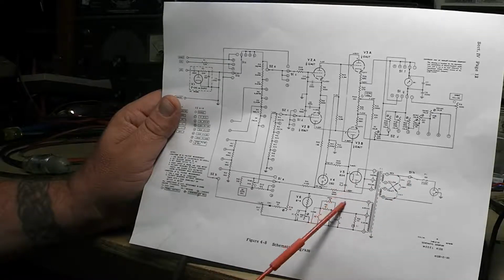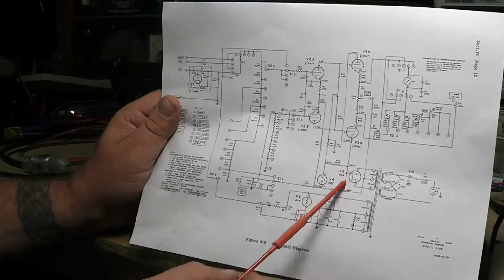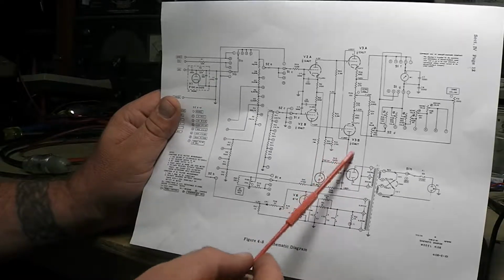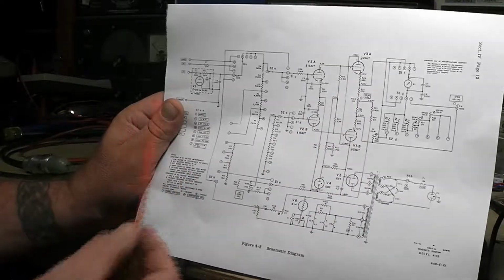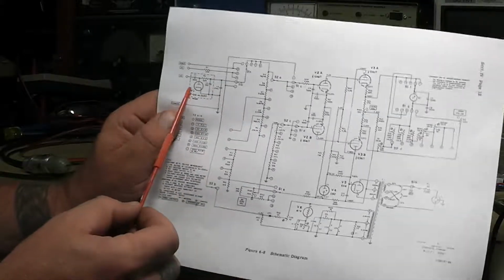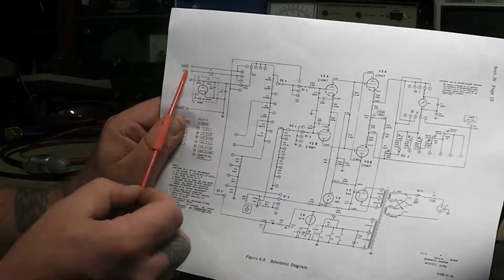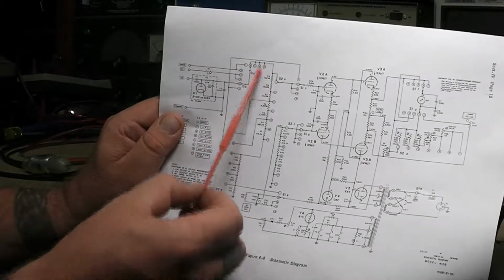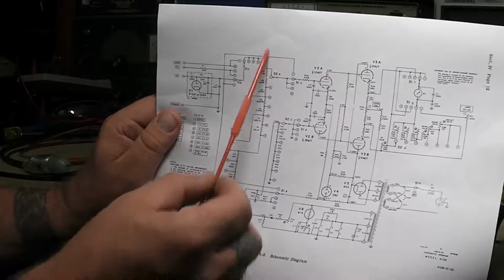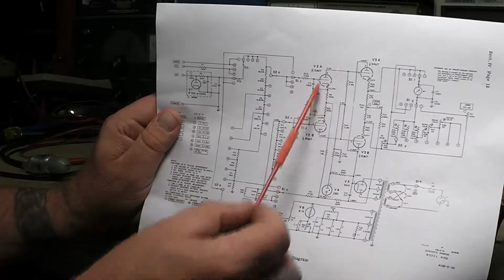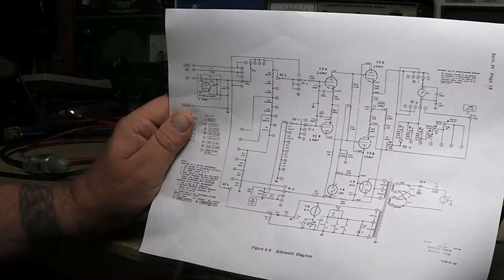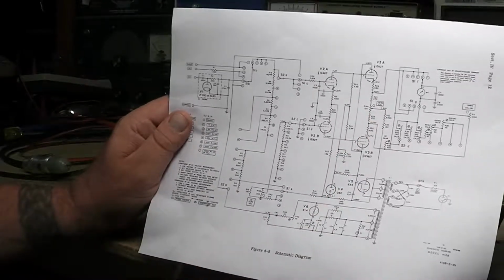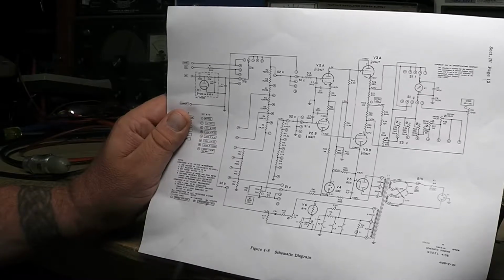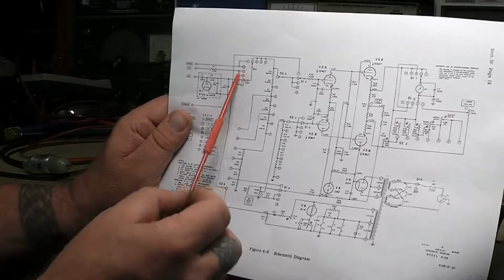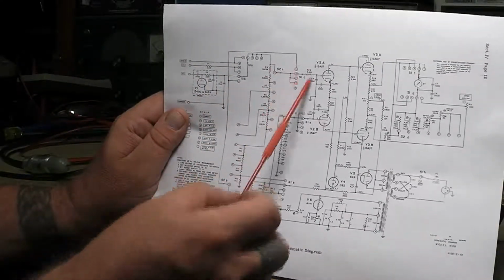Your heaters, there's your 6X4. You got your high voltage coming off here, 165, going to your bridge, your 12AU7, and then here's a picture of that tube and the probe, and your ohms are coming out here and tying into this, your divider for this, and then that would feed in to the bridge. And you have on the other side, here's your zero adjust for your ohms and DC. There's your DC, see it's over here, ohms and DC coming through here.